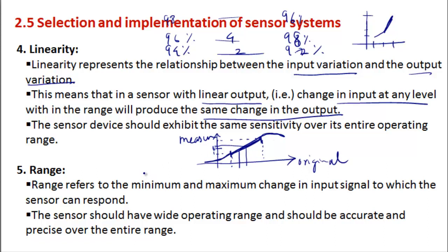If you have a pulse oximeter that people are using for COVID, just look at the data sheet or data manual of that. Most of the oximeters say that the value is not linear below almost 73-74 percentage, or in some cases even 79 percentage.